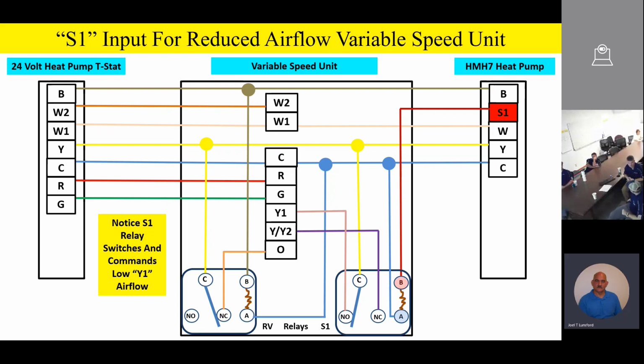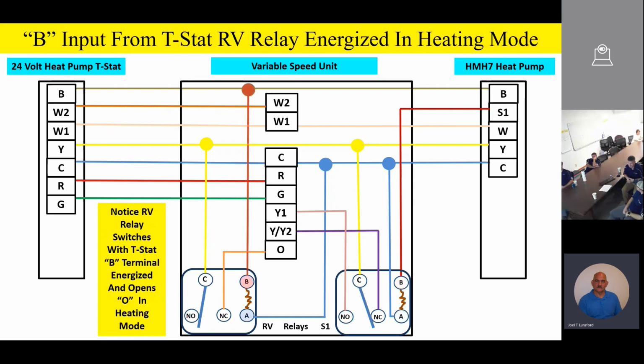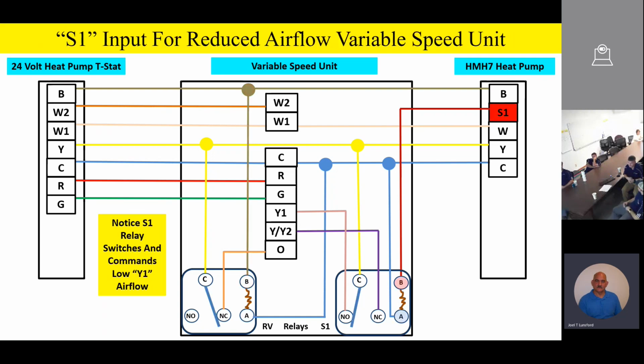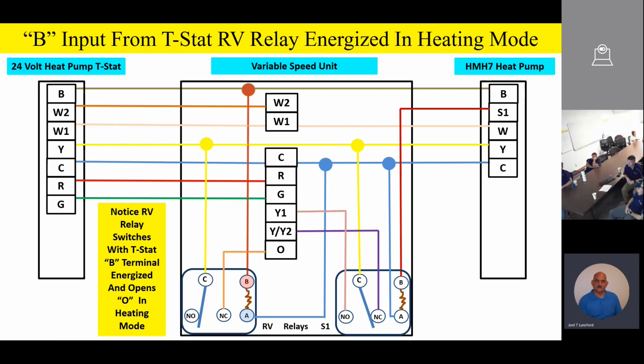On the RV relay, watch the RV relay. When we go into the heating mode of operation, when we energize the B terminal, you'll notice, bang, we're going to energize that RV relay and we're going to break that O signal. And we talked about why we did that. The only thing that RV relay is doing is breaking the O signal in the heating mode of operation, because the O signal drives some advanced functions in the cooling mode.